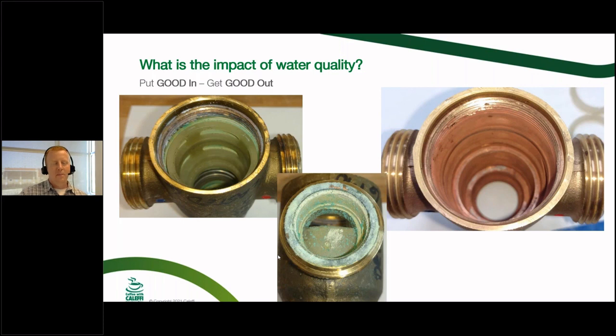Okay, this guy here, it was in probably one of the worst scenarios. Now we all know that magnesium and calcium want to precipitate out of solution as the temperatures get higher. That's why you got scaling. That's why your 40-gallon water heaters turn into really giant boat anchors, because they're filled halfway up with sediment and debris and everything like that and scale. That's why you have these water heater graveyards in old farmhouse basements, because nobody wants to take them back up the stairs. And again, same thing holds true with your mixing valves. If you've got hard water and you've got the potential for scaling, your mixing valve is going to be susceptible to it as well at some point.